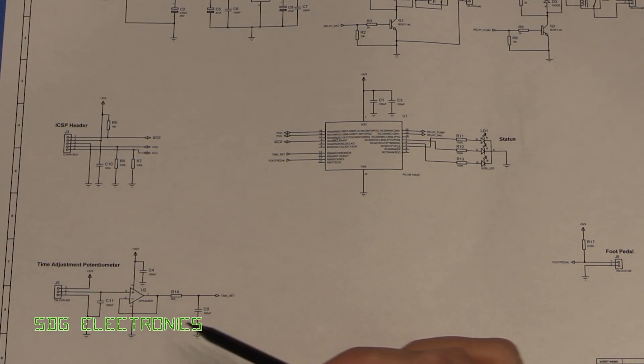And then we've just got a little bit of analog electronics here. So this is basically just a buffer and a filter and that takes in the input from a potentiometer that's on the front of the device and that sets how long it is before the pump turns off after releasing the foot pedal.